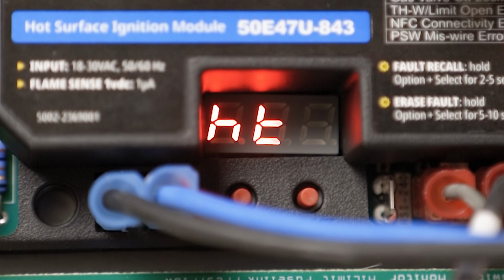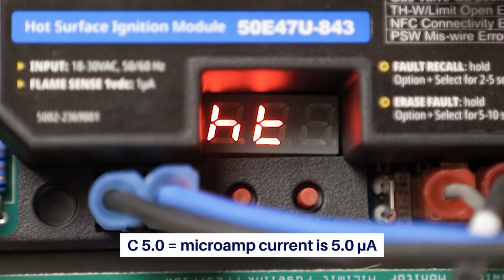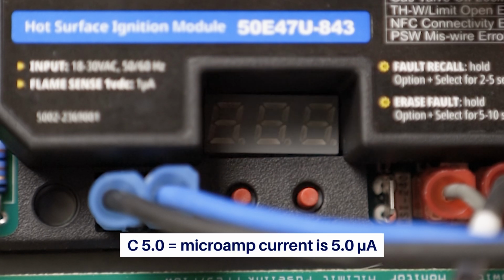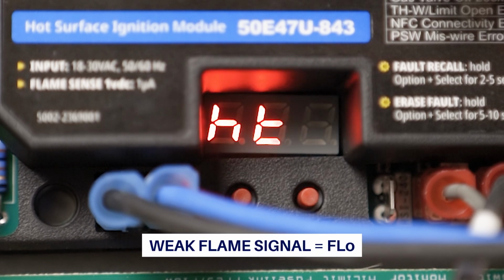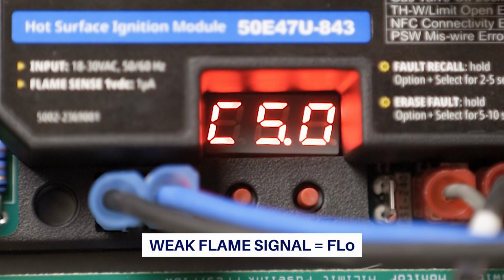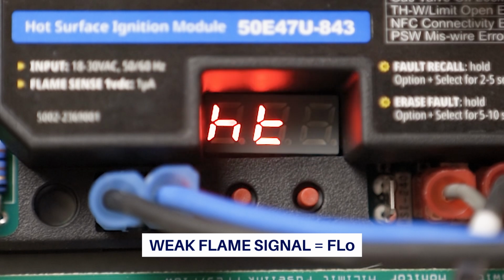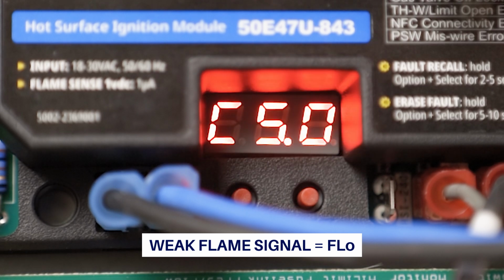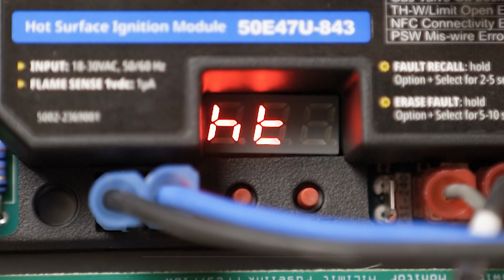After the flame is active, the display will flash between the letters H and T, indicating it is in the heat mode, and an uppercase C followed by 2 numbers separated by a dot or decimal. The numbers following the C are the real-time measurement of the flame current. In this application, the flame current reading is 5.0 microamps. When a weak flame is sensed during operation, the display will toggle between the letters HT and FLO, indicating the flame probe needs checked.